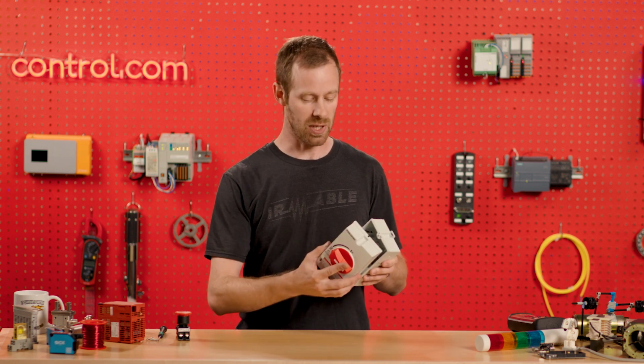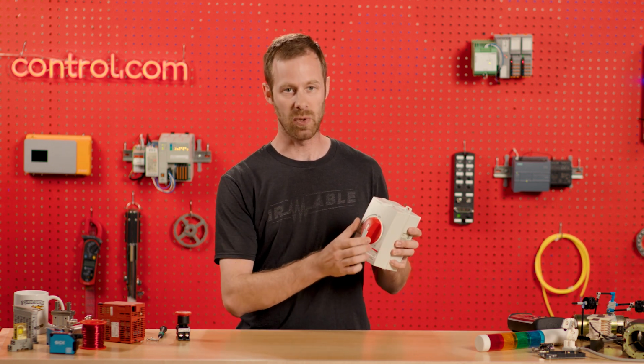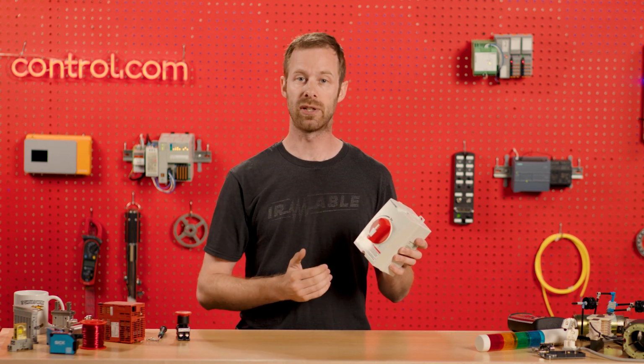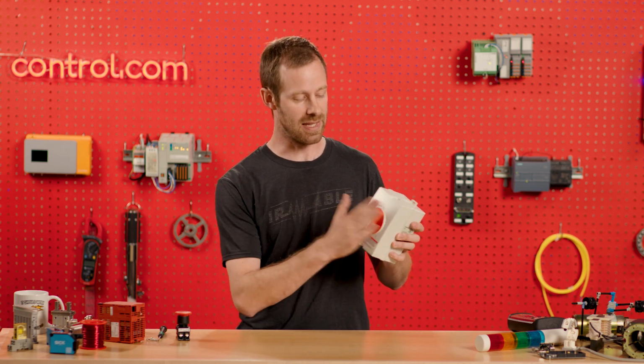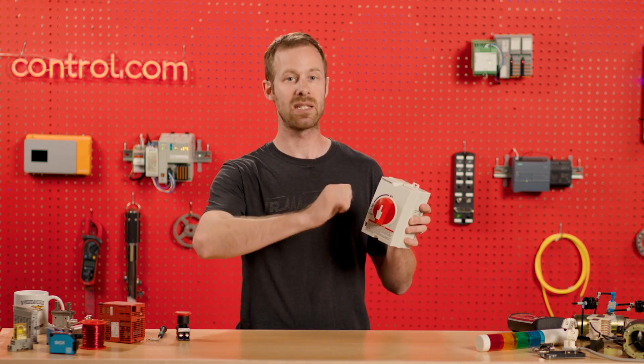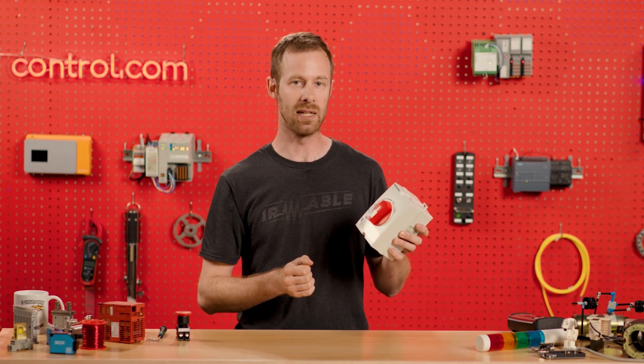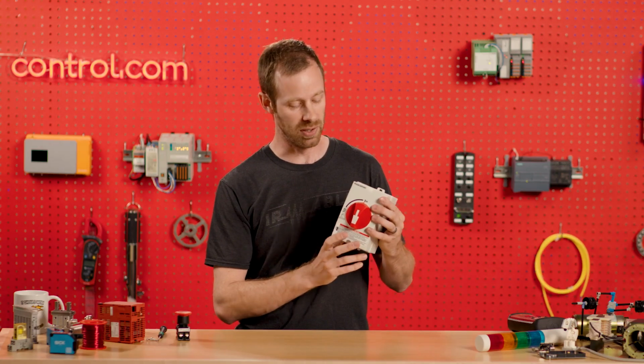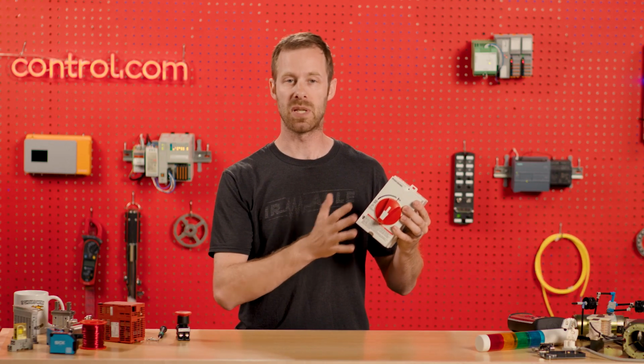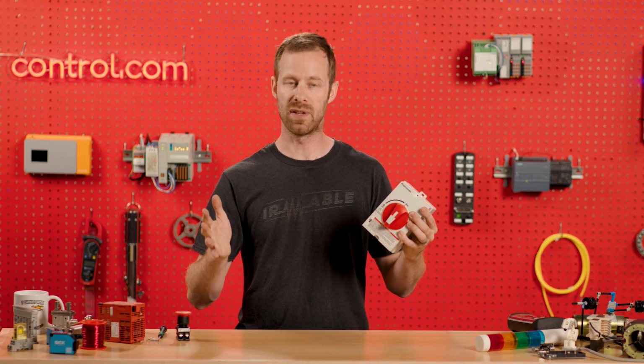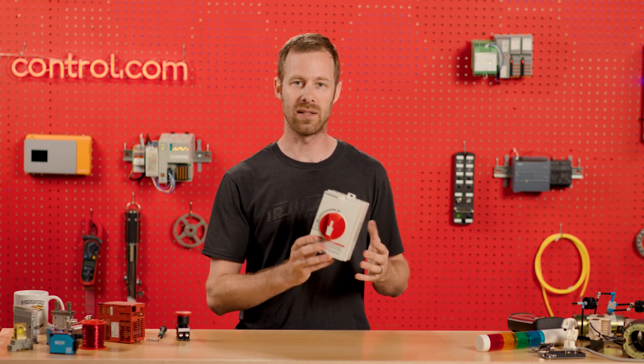So instead, that's why we use a disconnect switch along with circuit breakers and fuses, because this is the piece that's designed to be switched on and off repeatedly. The others exist solely to protect the downstream equipment and the operators from any damage. So disconnects are really important as part of an assembly to supply electricity to a device or a sub-assembly that's electrically controlled.